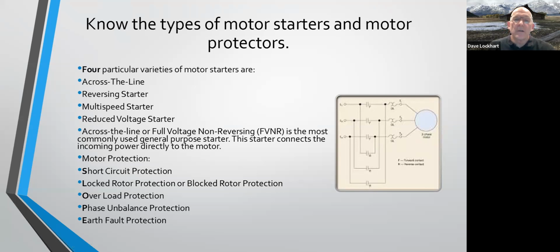And those will be in your motor control center, your MCC. Sometimes it'll be in your breakers and other things, just to make sure that if that motor has a certain situation, it'll open up and protect that motor from burning out and failing or causing other damages. So pretty straightforward. Short circuit is pretty straightforward. Instead of that motor frying, hopefully that short circuit will open quick enough to protect that.